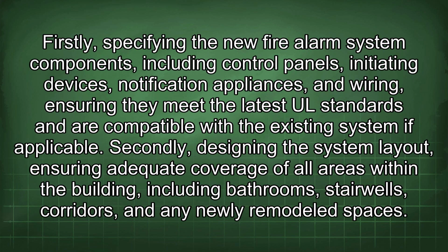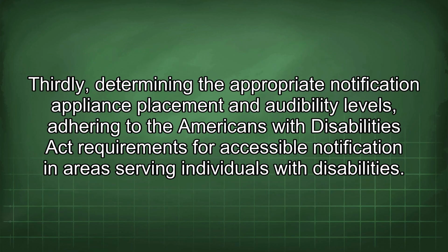Firstly, specifying the new fire alarm system components, including control panels, initiating devices, notification appliances, and wiring, ensuring they meet the latest UL standards and are compatible with the existing system if applicable. Secondly, designing the system layout, ensuring adequate coverage of all areas within the building, including bathrooms, stairwells, corridors, and any newly remodeled spaces. Thirdly, determining the appropriate notification appliance placement and audibility levels, adhering to the Americans with Disabilities Act requirements for accessible notification in areas serving individuals with disabilities.